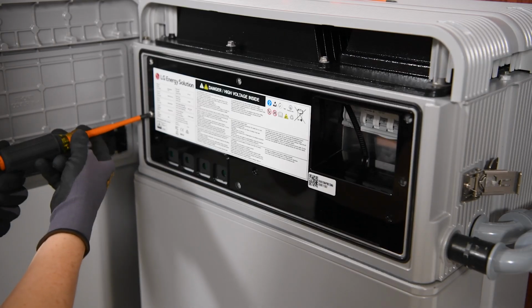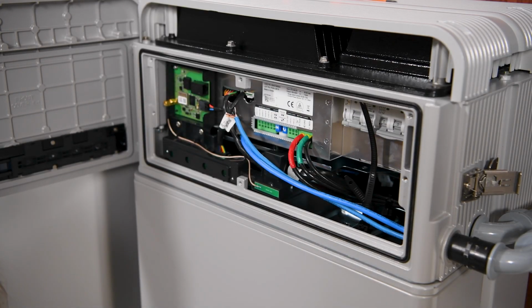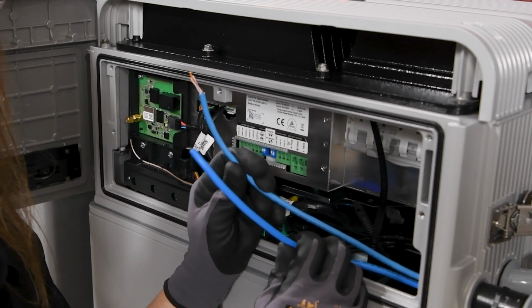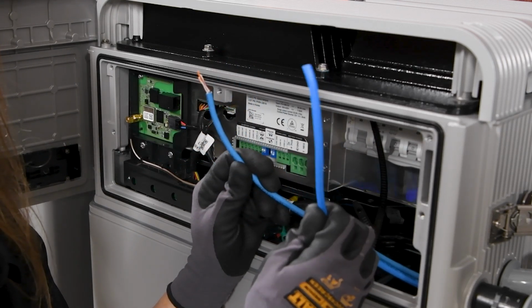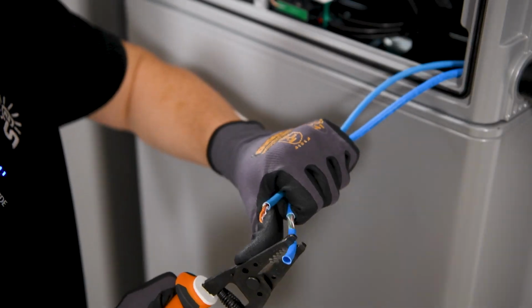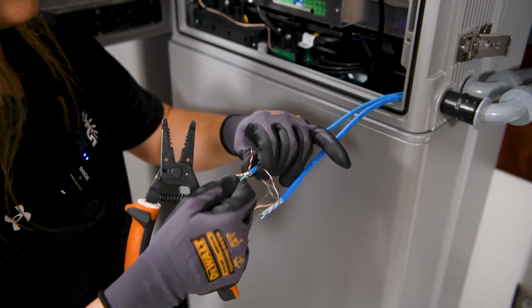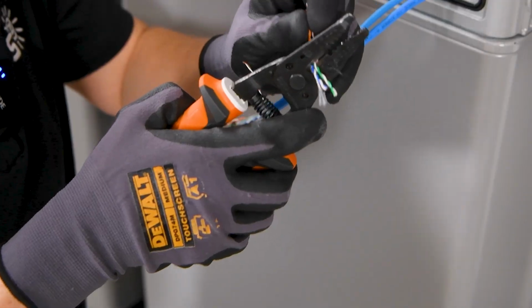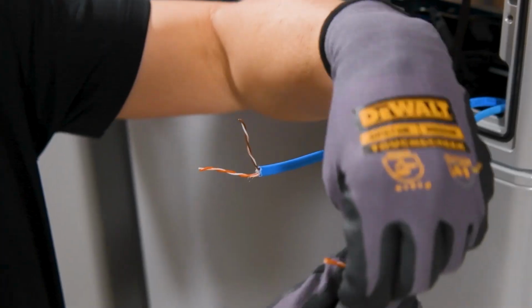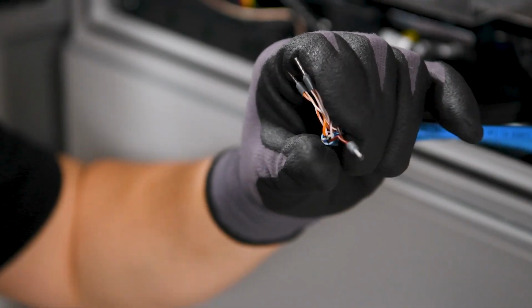Now we're going to connect the communications for our secondary battery. We have communications coming from our primary battery, and communications already connected for our inverter. We'll combine both of these communications cables and connect them to our secondary battery, which will parallel both batteries so they can communicate with the inverter.